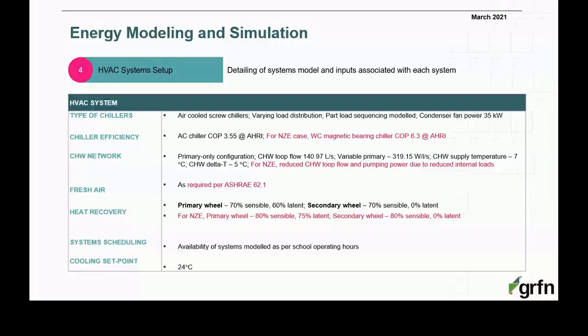Fresh air, or the outside air, was as per ASHRAE 62.1 requirements. For the heat recovery, in the original case, the primary wheel had 70% sensible efficiency and 60% latent. The secondary wheel had 70%. For the net zero energy case, the primary wheel had 80% sensible efficiency and 75% latent efficiency, and the secondary wheel had an 80% sensible efficiency. For system scheduling, the operating hours followed the school, and the cooling set point was 24 degrees C.